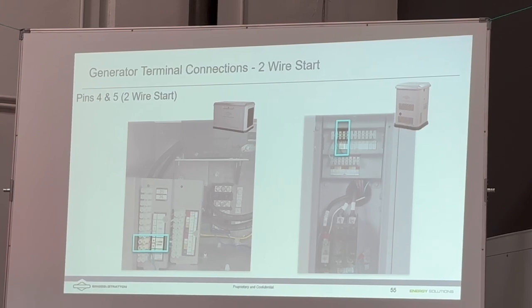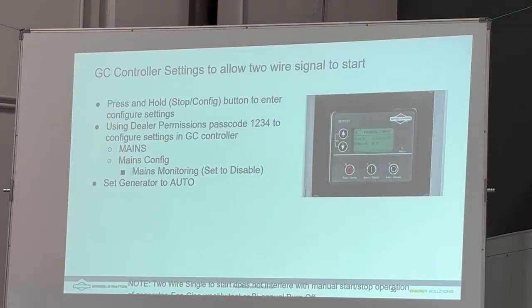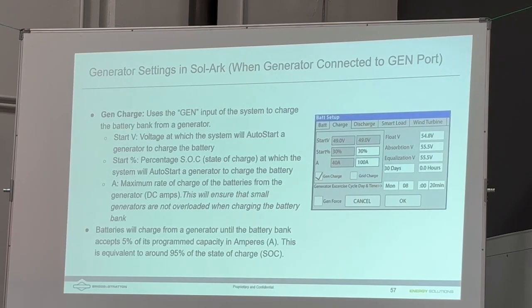It will only do that when the grid is down. So it won't do that if utility power is there. You cannot parallel the generator to the grid, right? So you can only do that either in an off-grid situation or if the grid port's inactive. This is a little explanation based on time. I think I've got about 20 minutes left. I'm not going to go through how to do this, but basically you just go into this controller. It tells you how to do it here, and you would disable auto main sensing and enable 2-wire start. That lets the Sol-Ark control the Briggs generator.